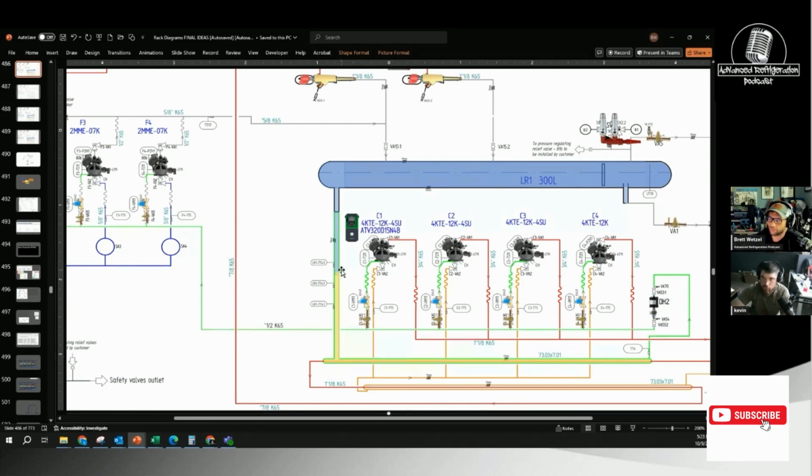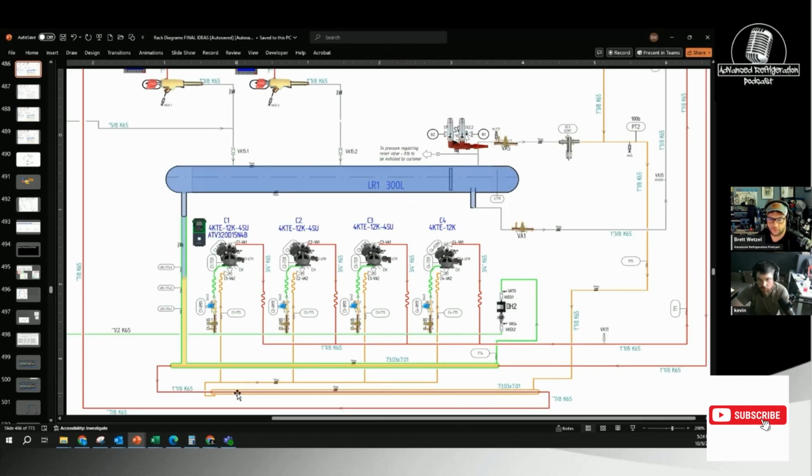And so that's what they're doing. They're warming up that 36-degree oil by taking the drop leg temperature and running it directly through this heat exchanger to warm it up. And that's what this one's for. That's to mitigate any low superheat that you might get from your BGV or your medium temp cases. Yeah, except when you have no load, it doesn't work. Oh, the heat exchanger? Yeah. That's no good.